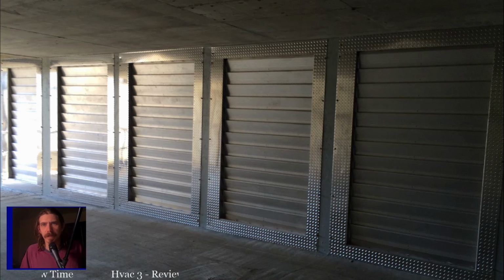But the main reason is it allows us to run it easily. When you get into high voltage, technically you're supposed to be an electrician to run those, and I think codes add to the reasons, even though I don't think it's anywhere near the primary reason. But we use 24 volts mainly because these things are easy to install and easy to mess with, and it's less of a headache than using higher voltages. And a lot of the electronic components are made for those lower voltages for a ton of industry reasons. But it's mainly just because it's easier to install. I guess the components being easier to install is the biggest reason.